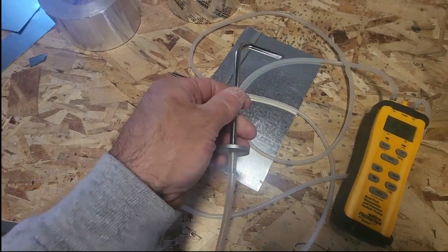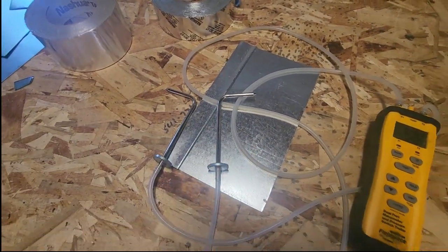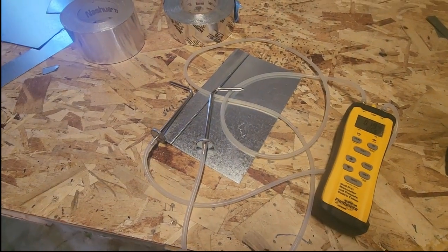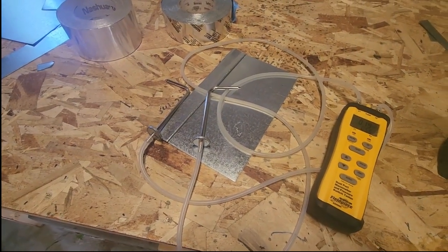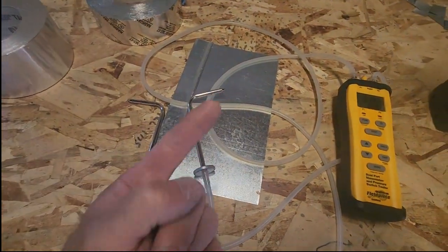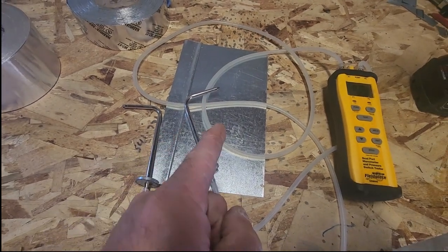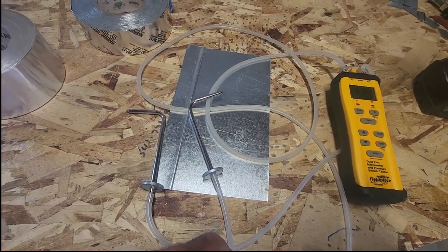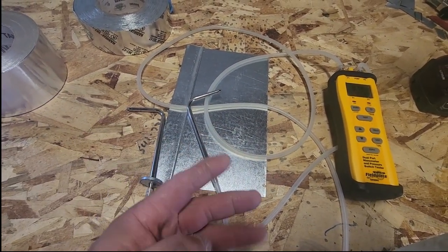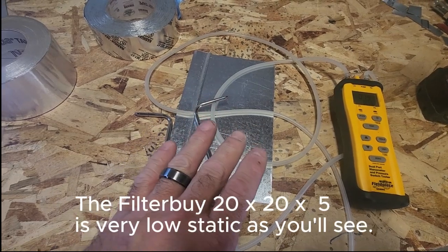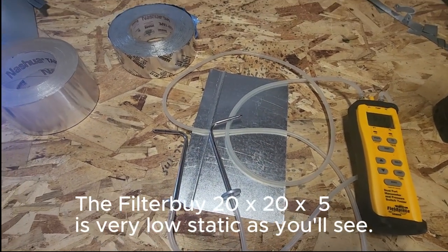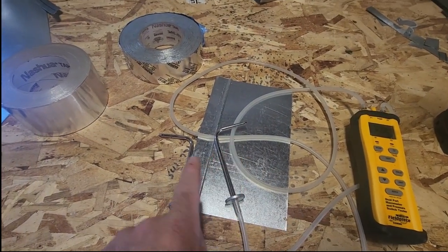This is going to be kind of interesting because I'm going to be able to show you total static pressure. I have 2 zones on my zone system, so I'll be able to show you what it's like with one damper open, one damper closed, and everything open. I'm going to do it with the filter in and the filter out, so you can see what kind of static pressure these 5-inch filters have.